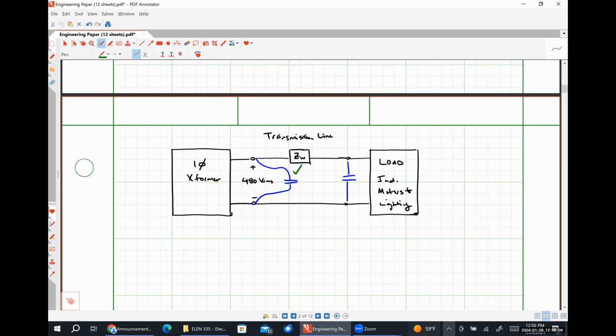The reason it's done at the transformer versus at the load is because, A, our transmission line is also going to have some inductance, which will influence our power factor. So correcting our power factor at the transformer takes into account all of the inductance of our load as well as all of the inductance of our transmission line.